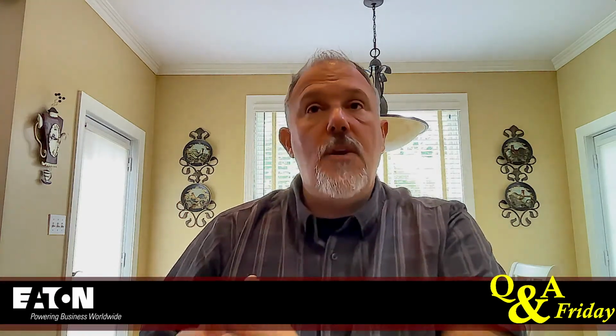Walter Gonzalez, wow, that's profound, buddy. And that's an interesting perspective, because when I get into this discussion, when we start teaching NFPA 70E, and we talk about incident energy, and we talk about 70B maintenance and maintaining circuit breakers, the problem I have with adding additional time, how much time do you add? Where do you get the number from?